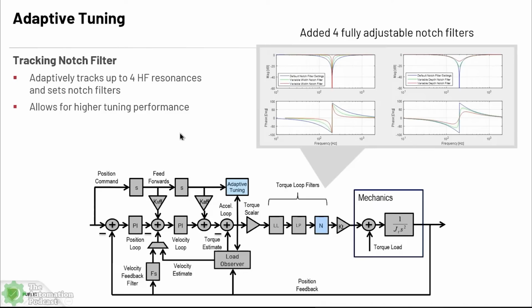With adaptive tuning, we think about the frequencies that are outside the band—Load Observer finds those that are in band. What we've learned is the harder we tune our drive for performance using Load Observer, the more stress it puts on the mechanical system. We don't want additional stress, so what we're really doing is finding those resonant points in the mechanical system as a result of optimizing overall performance. Adaptive tuning finds all those frequencies outside of band, the higher frequencies creating resonances, and tunes them out.